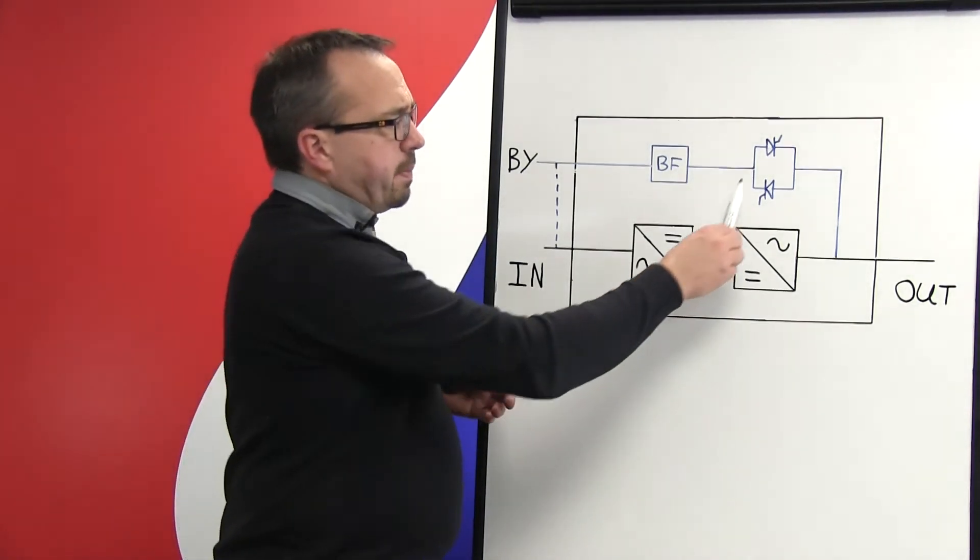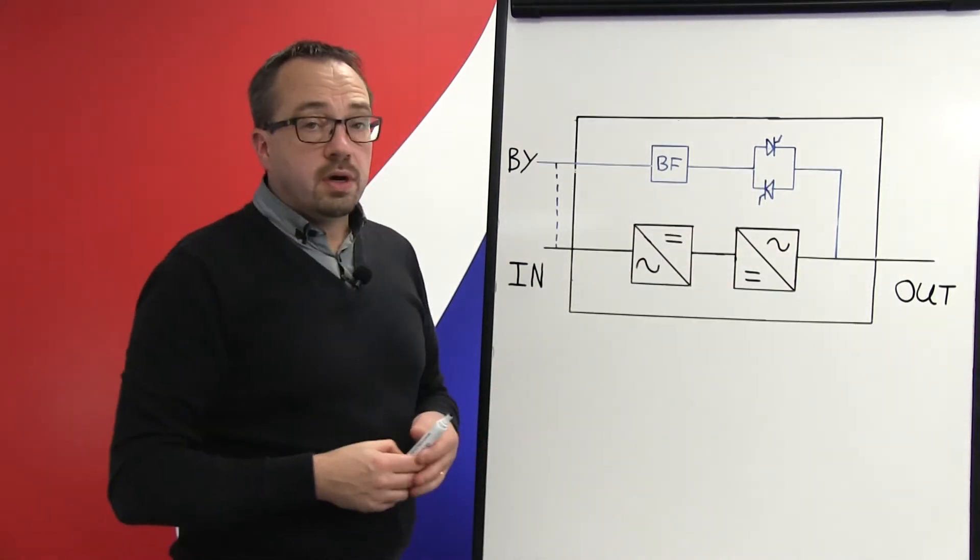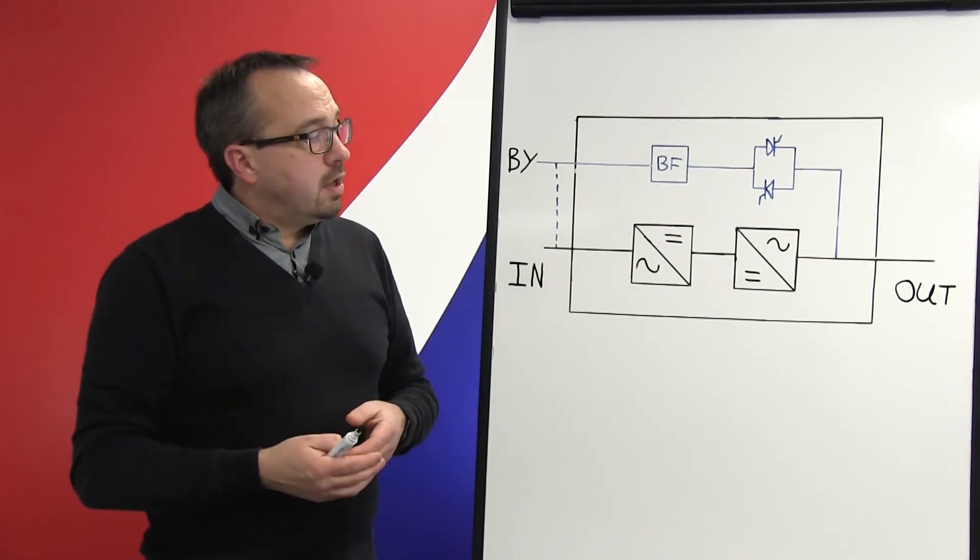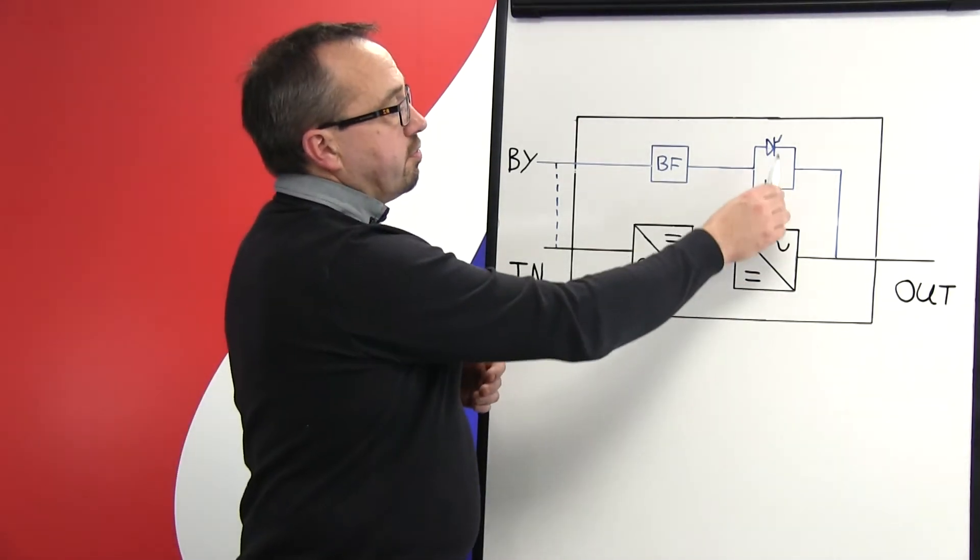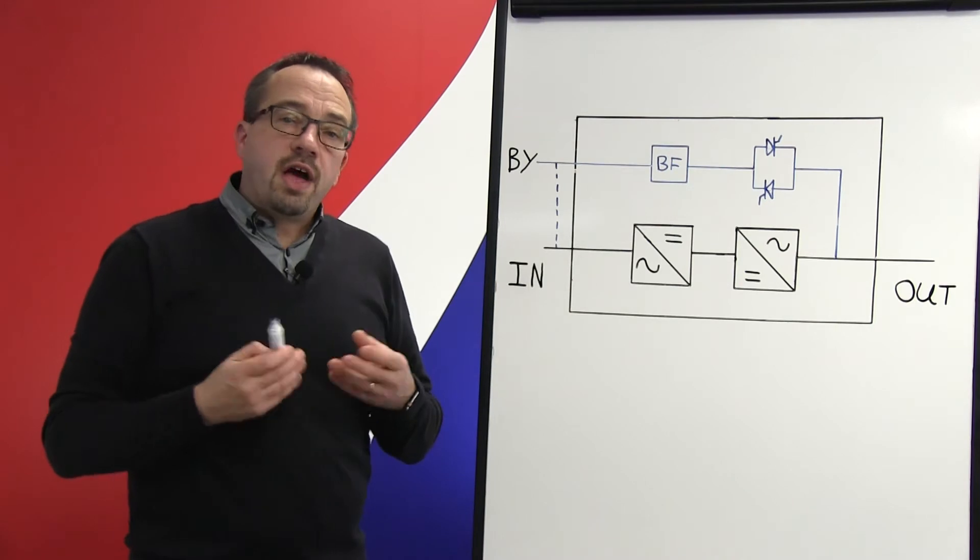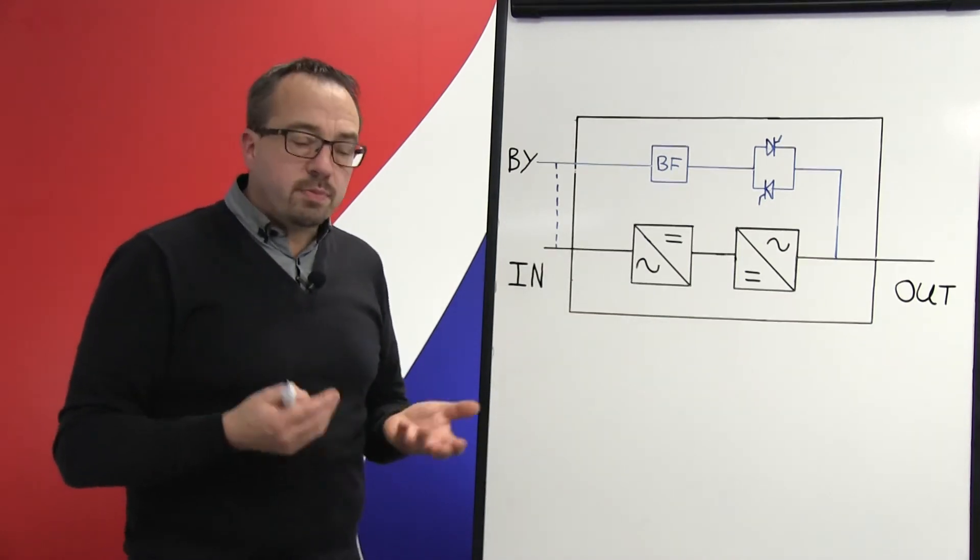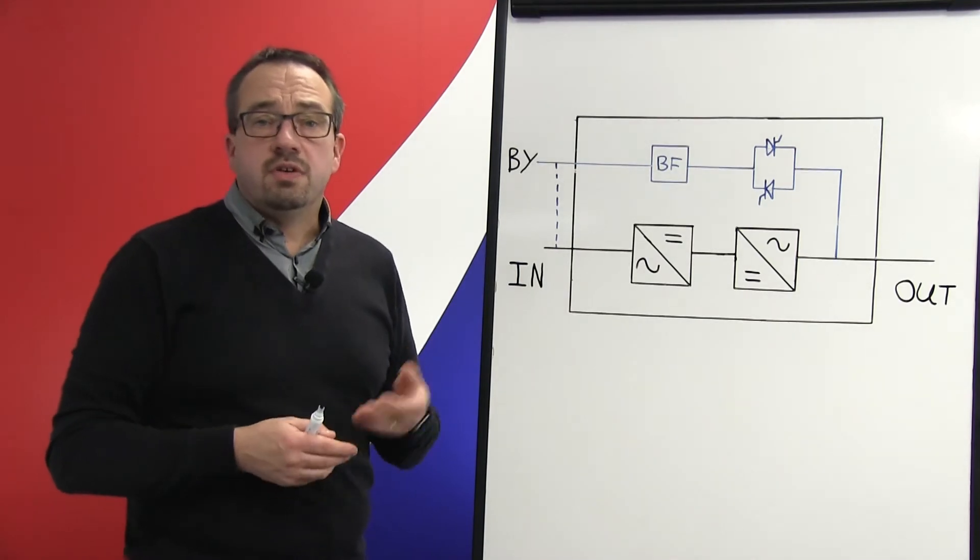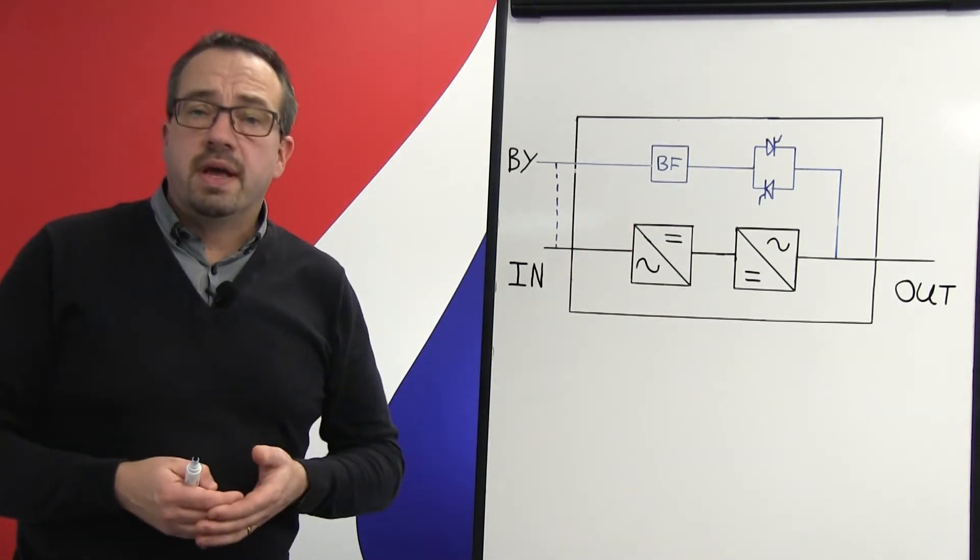Now the static bypass switch itself is so called because it's effectively got no moving parts. It's static and it's not like a mechanical switch. It basically comprises of two components referred to as thyristors. Thyristors over many years have proven themselves to be a highly reliable component, hence a perfect component for this kind of application.